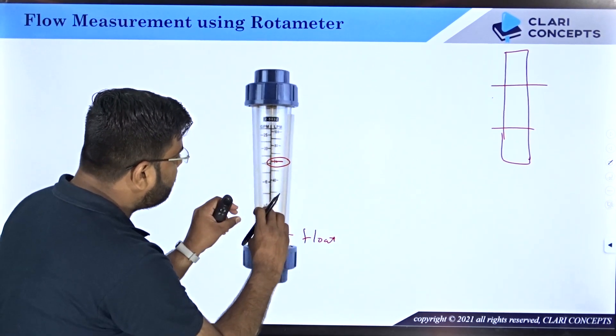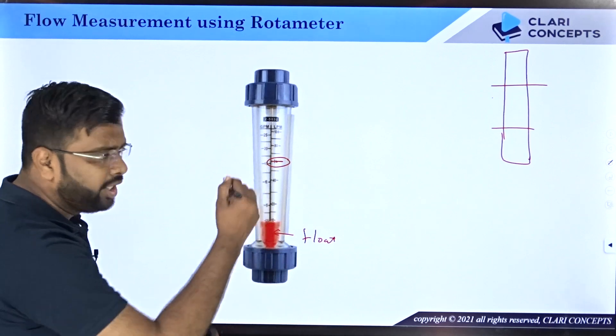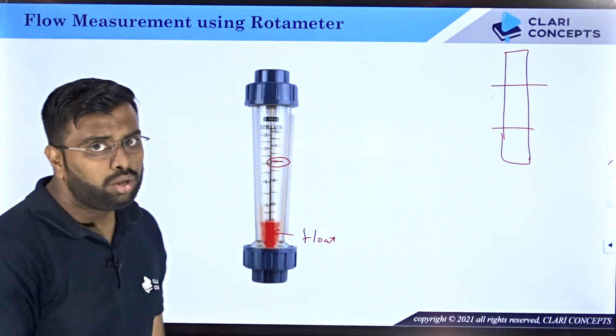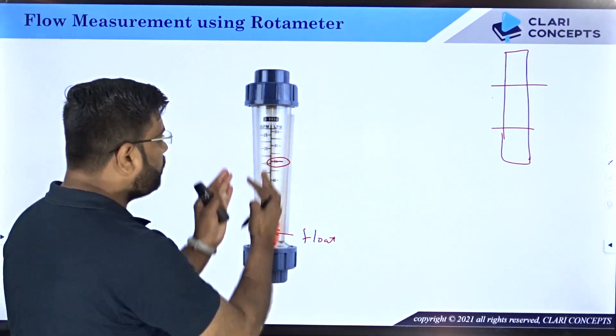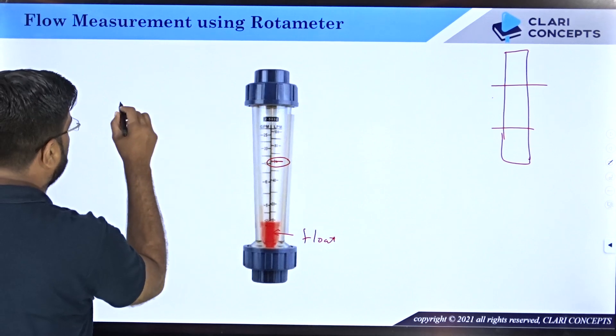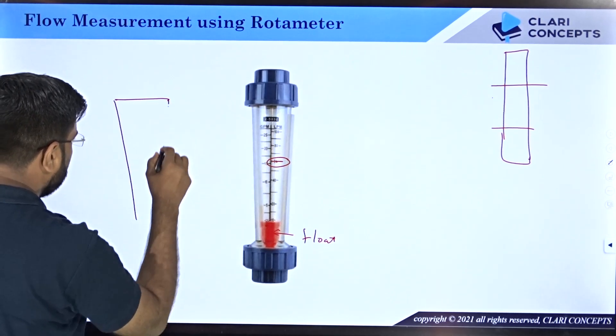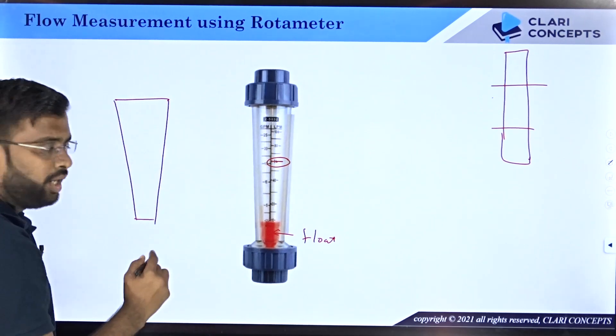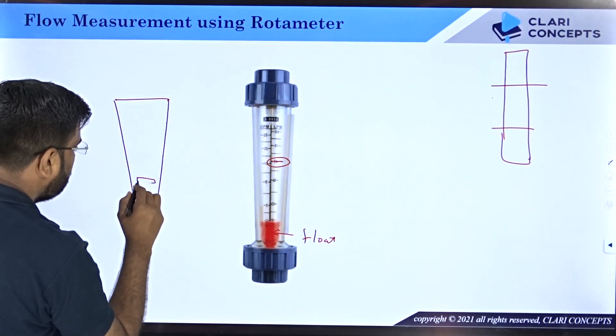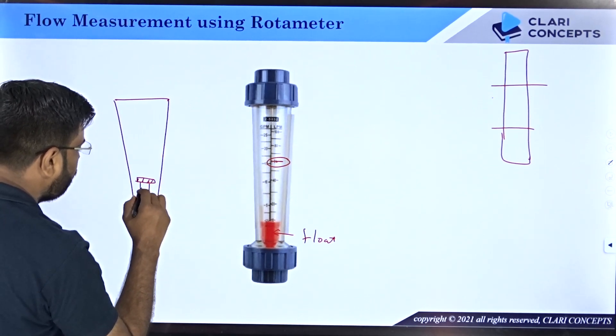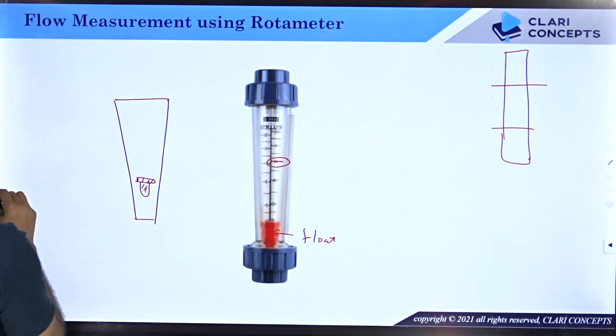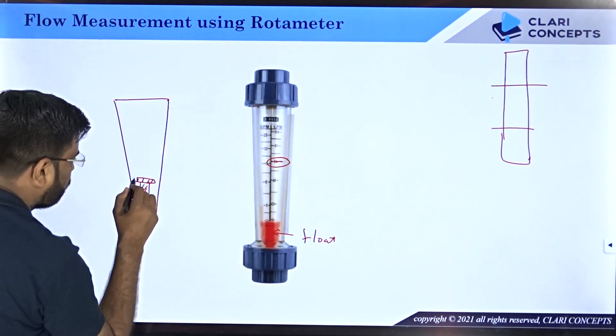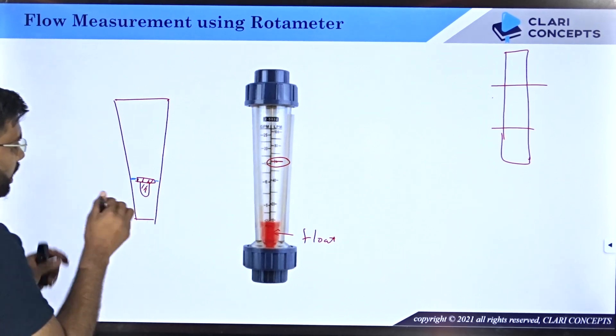Now the question is: how does the float adjust itself depending on the flow rate? The physics behind this is that the pipe in the rotameter is not of constant cross-sectional area — it has a varying, gradually increasing cross-sectional area. As the float moves upward, the area around it increases. The float has a specific diameter, and the area available for water to pass is only the annular ring between the float and the tube wall — all the water passes through this annular region.